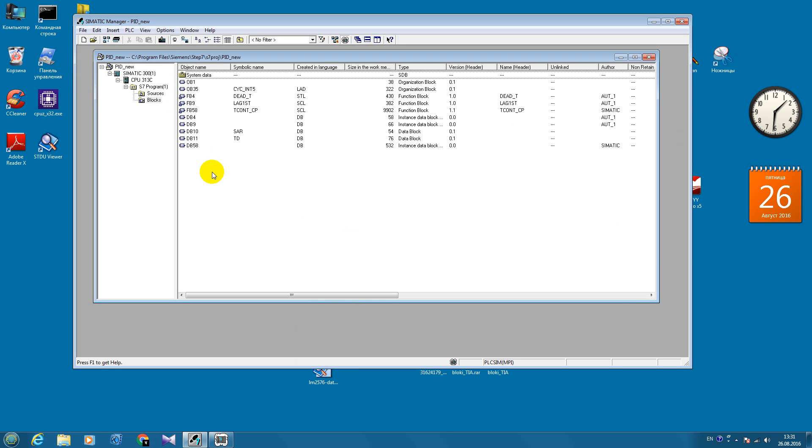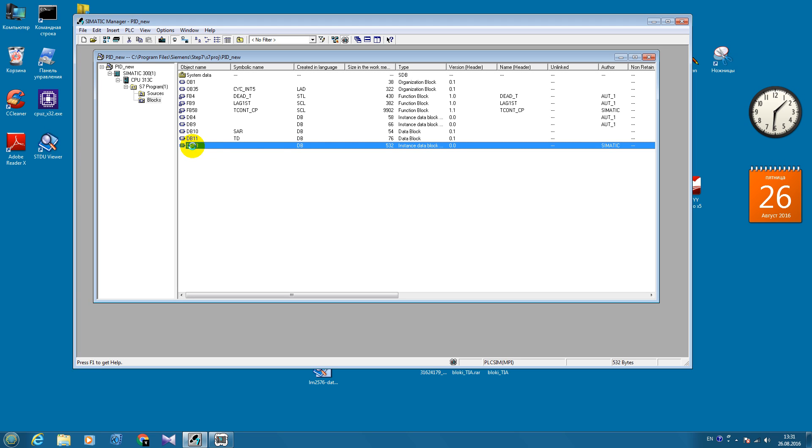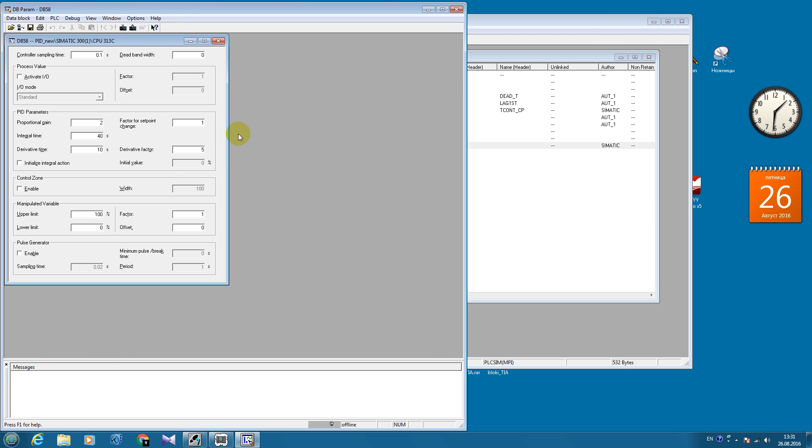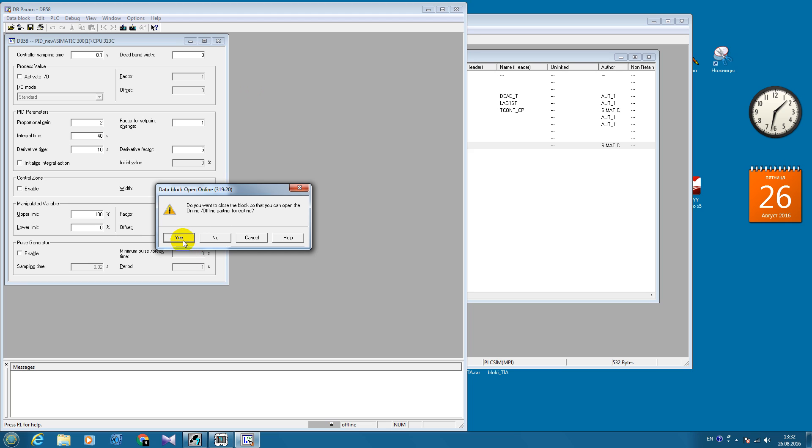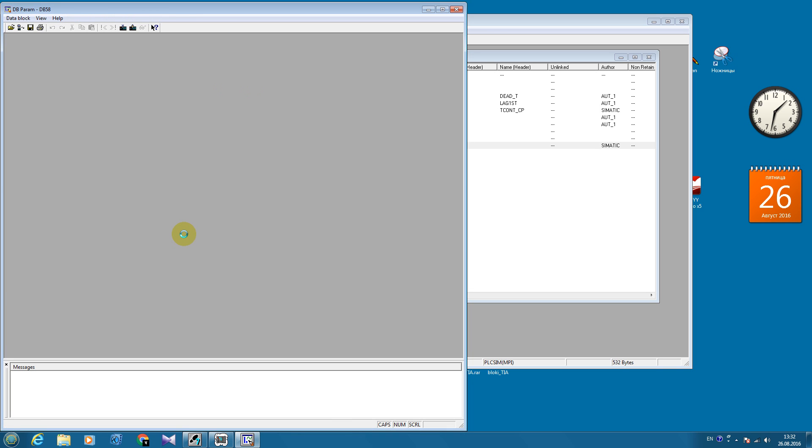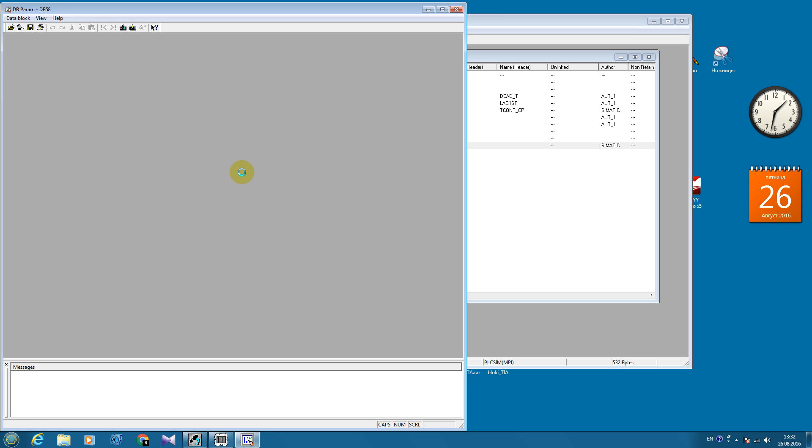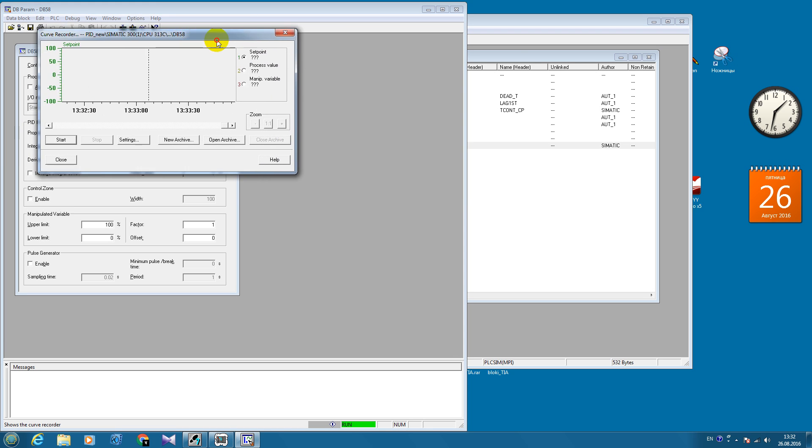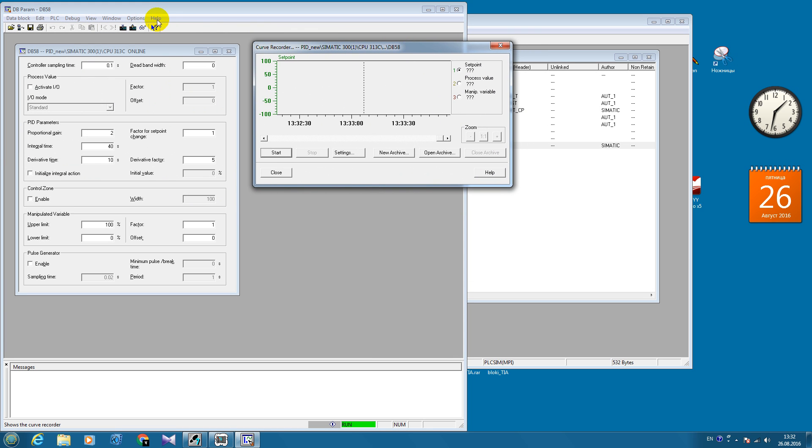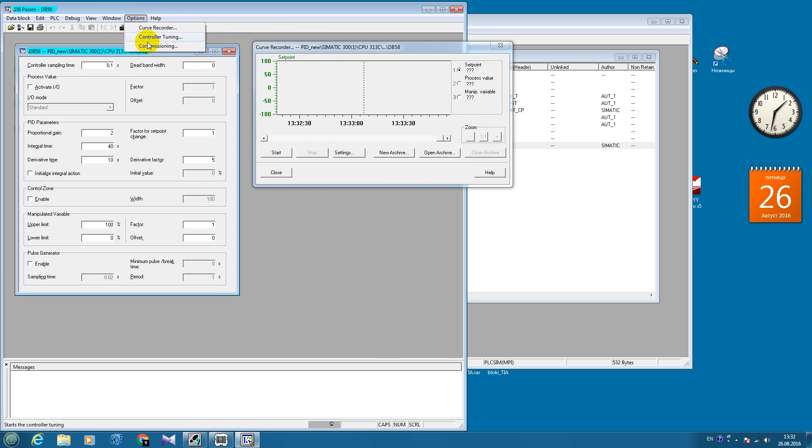Now you will see why I use PID controller represented by function block 58. Because it has very good interface for the tuning and to see the transient processes. So it's very useful. Now I'm going to go online with this block. And here in the options menu, I'm going to choose curve recorder and commissioning menus.